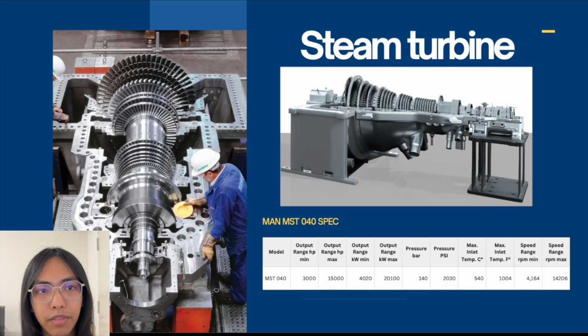For the steam turbine, we tried to find an industrial turbine that aligns with our calculated spec for the steam turbine, fuel consumption, and energy output, which means we came up with the MAN MST040. We have the spec: output range from 3,000 horsepower to 15,000 horsepower, with energy output range from 4 MW up to 20 MW, with a pressure of 140 bar, max inlet temperature of 540 Celsius, with a shaft speed from 4,300 up to 15,000 revolutions per minute.